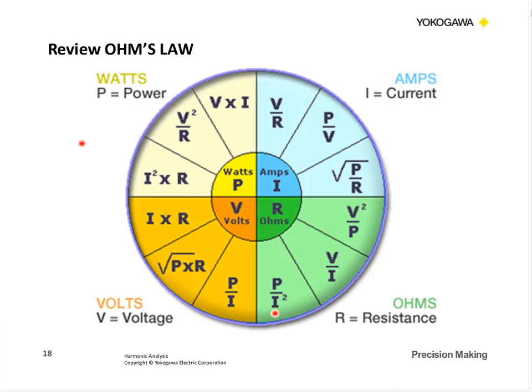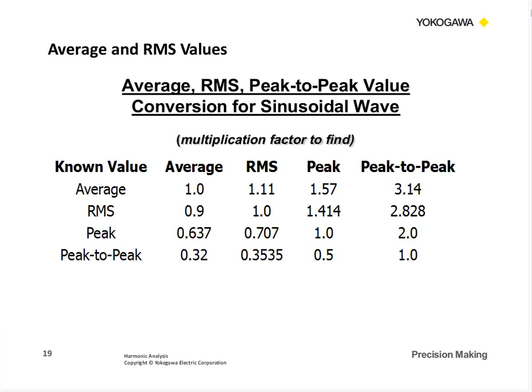And then, of course, there are other parameters that you can use with Ohm's law, but we're going to be talking about basically the power, the voltage times the current. A couple things that we want to review, and we will use sometimes in our measurement, is the comparison between the average, the RMS, and the peak-to-peak values, and this relates to a sine wave. So if we know the RMS value on a sine wave, we know that peak is square root of 2, 1.414. Now, the other function that we use quite a bit in some of our measurements is this average, or half cycle average.